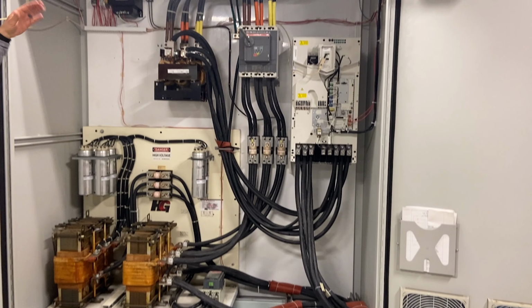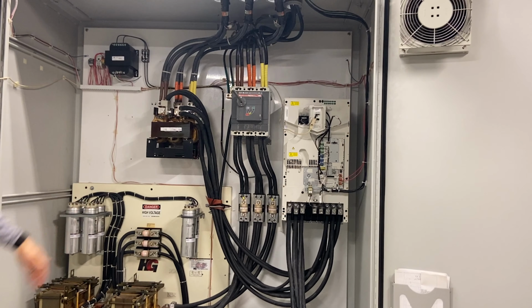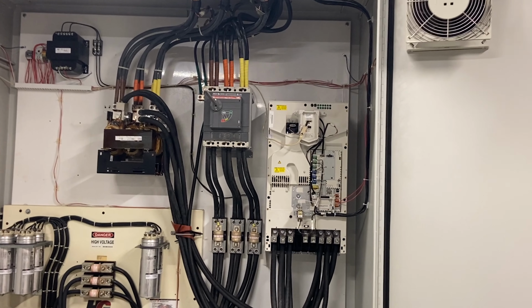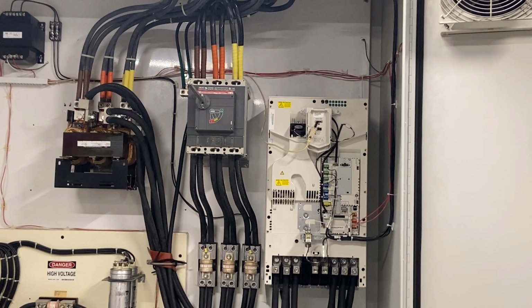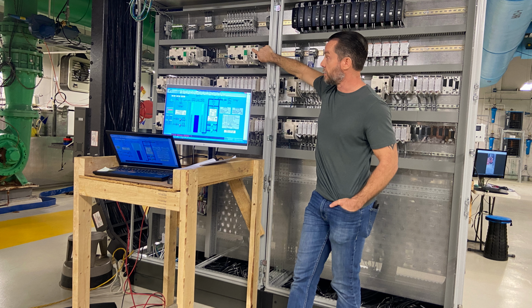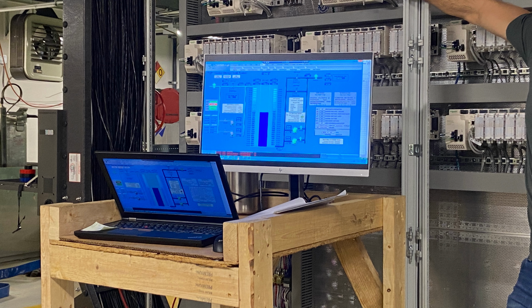Another way UNC chilled water services saves a lot of money and energy is through the variable frequency device, or VFD. It takes less energy to run 2 motors at half the speed than 1 motor at full speed. Using this knowledge, the VFDs are programmed to use less electricity, which then saves money. VFDs have the ability to slow a motor down by sending less energy to it. These motors can be in chillers or the fans of cooling towers.